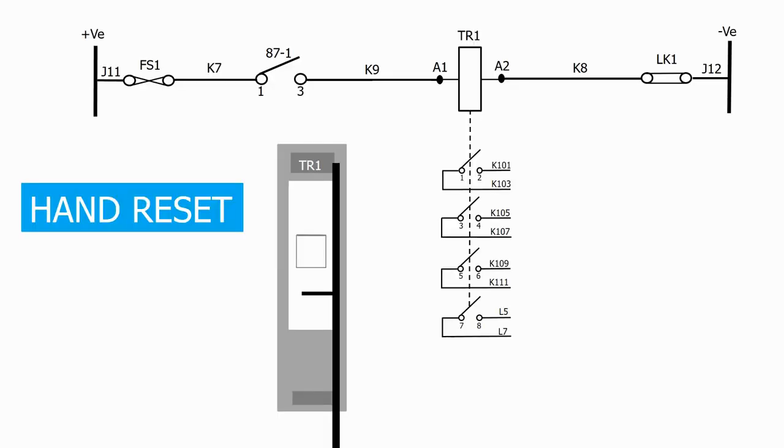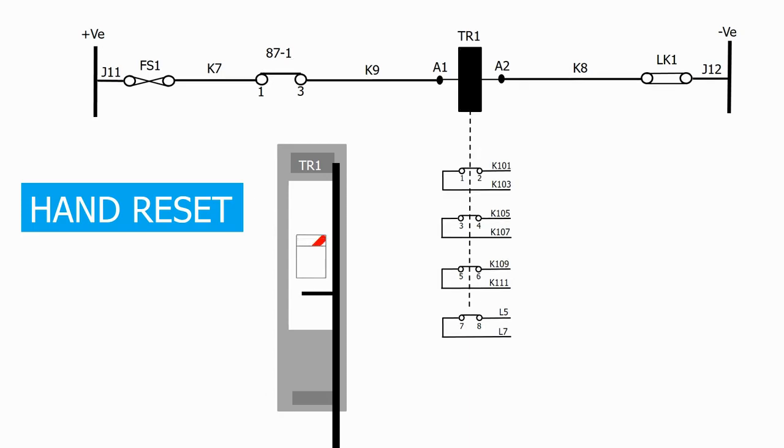Again, the flag and contacts operate when the relay is energized, but the contacts and flag don't change state when the initiation is removed and the relay coil de-energizes.